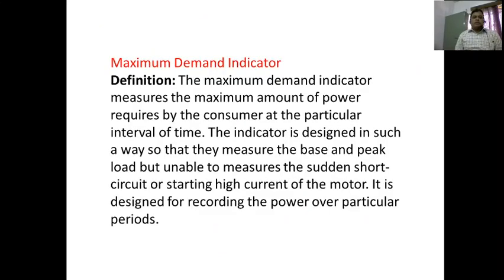What is a Maximum Demand Indicator? The Maximum Demand Indicator measures the maximum amount of power required by the consumer at a particular interval of time. The indicator is designed in such a way that they measure the base and peak load, but they are unable to measure the sudden short circuit or high current to the motor. It is designed for recording the power over particular periods.